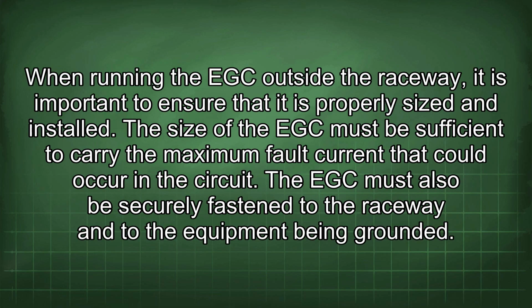When running the EGC outside the raceway, it is important to ensure that it is properly sized and installed. The size of the EGC must be sufficient to carry the maximum fault current that could occur in the circuit. The EGC must also be securely fastened to the raceway and to the equipment being grounded.